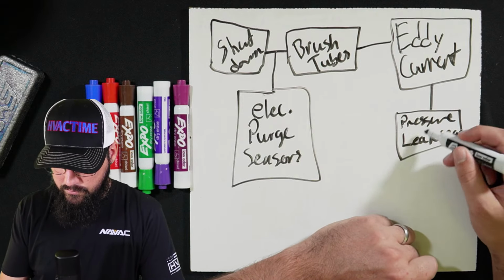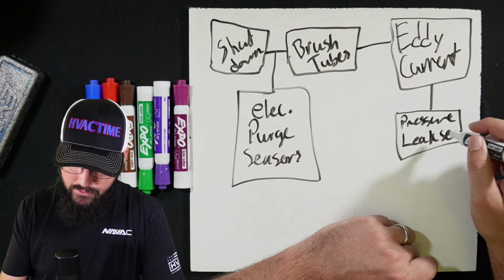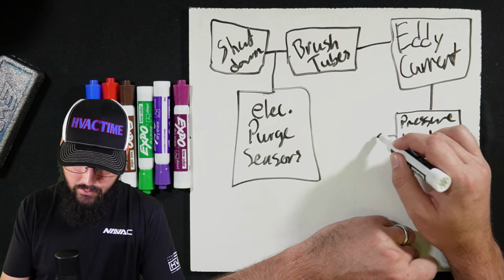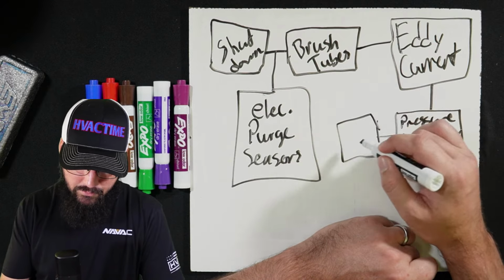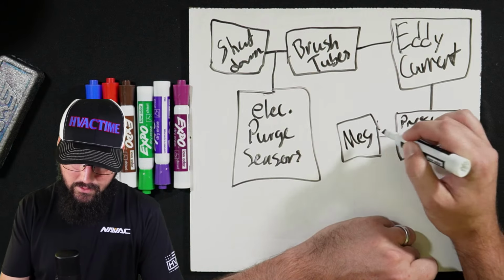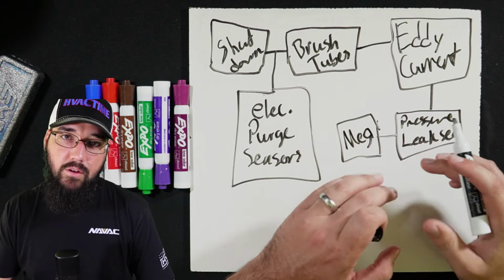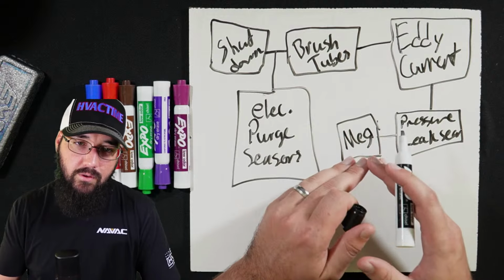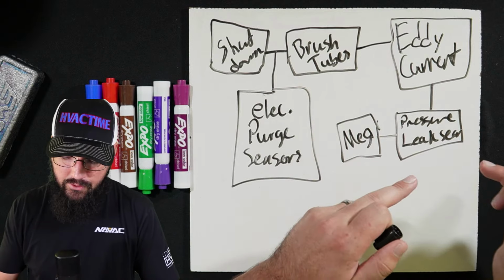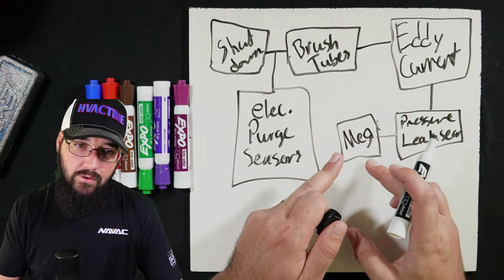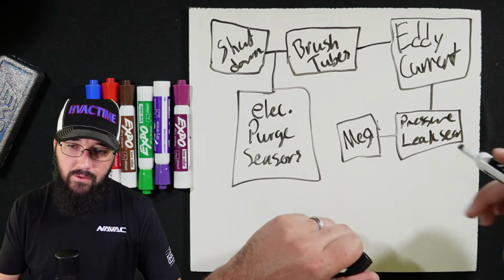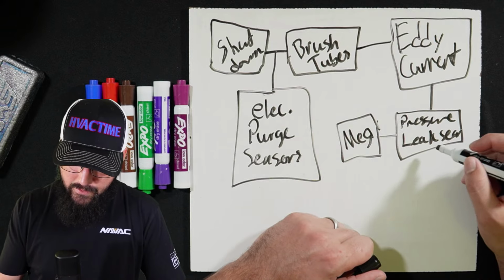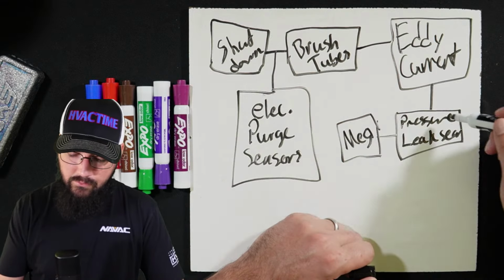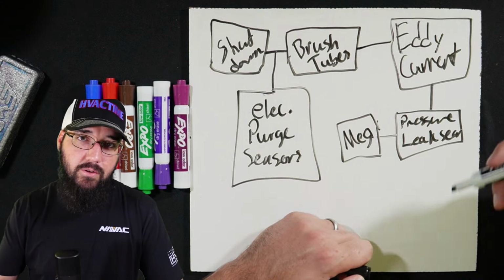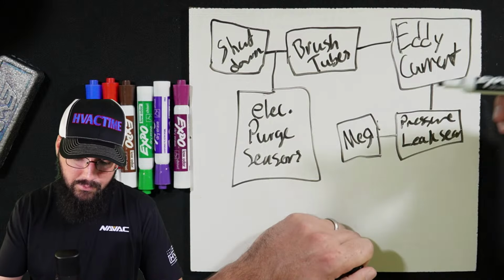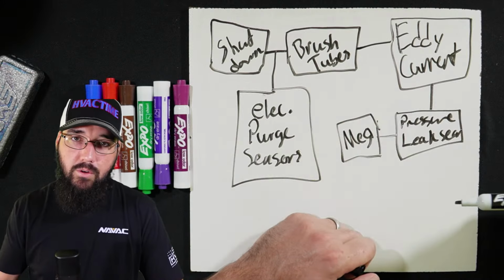Okay, so pressurizing and leak search. While we're pressurized, we also need to megohm the motor. We don't want to do this while it's in a vacuum. We want to do this when it's in positive pressure. When we do the leak searching, this is the time to do your megohm readings. That's where this guy over here comes in. This guy is setting up the pressurizer, getting it going. Once we're up to pressure, this is where you get involved.